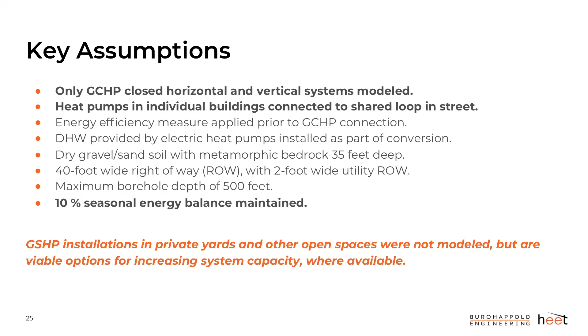This is a key point: we also assumed it would maintain a seasonal energy balance of about 10%. That means the amount of heat put into the ground and the amount pulled out during heating and cooling seasons is more or less the same. We did this to avoid thermal degradation—if there's an imbalance between heat going in and heat being taken out, it could lead to adverse conditions, freezing the ground or overheating it. That diminishes the system's capacity and efficiency, and can also cause environmental issues, which we wanted to avoid.